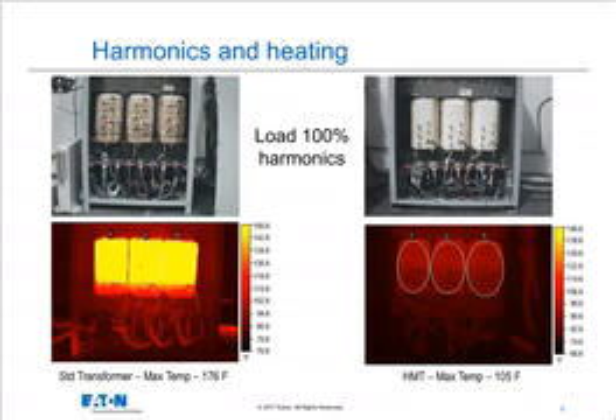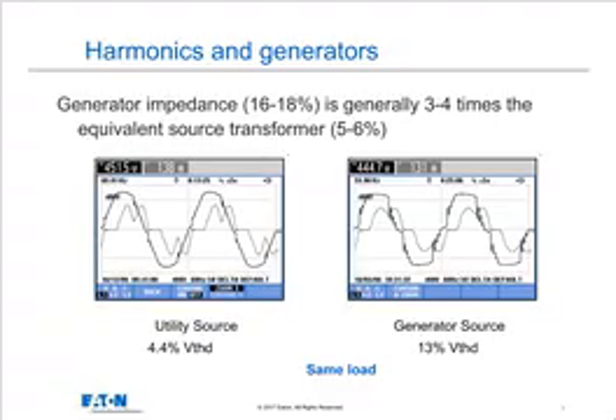The transformer on the right, that harmonic mitigating transformer, runs significantly cooler, and it can deal with the harmonics. It can actually run cooler with the harmonics running through it. But the fact of the matter is it costs more money. So it's either a capital expense budget or an expense budget over time that people have to deal with when they're dealing with harmonics. So they have to decide, do I want to spend more money up front, or do I correct the problem over time, or maybe derate the transformer?